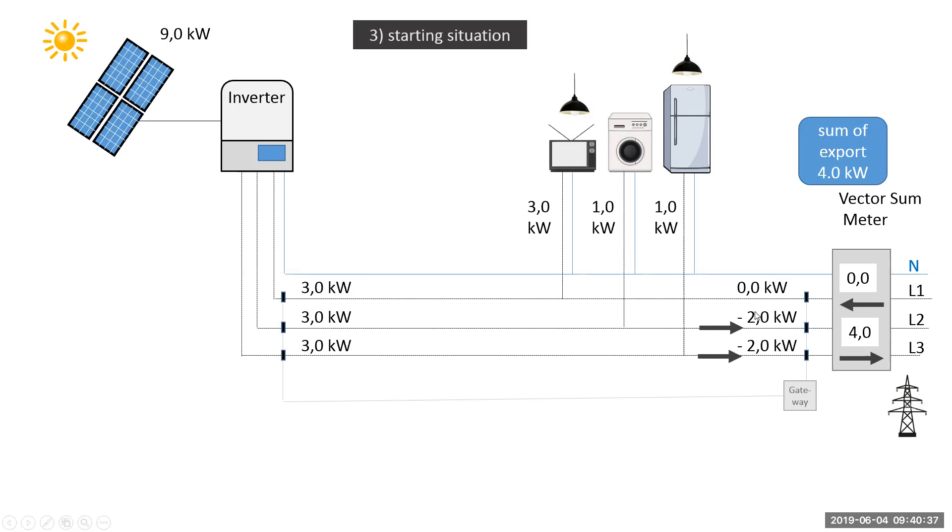Two would be going out on L2 and two would be going out on L3, and L1 would be equal because the three for that circuit and three that the battery is giving is zero. So the net export would be four.